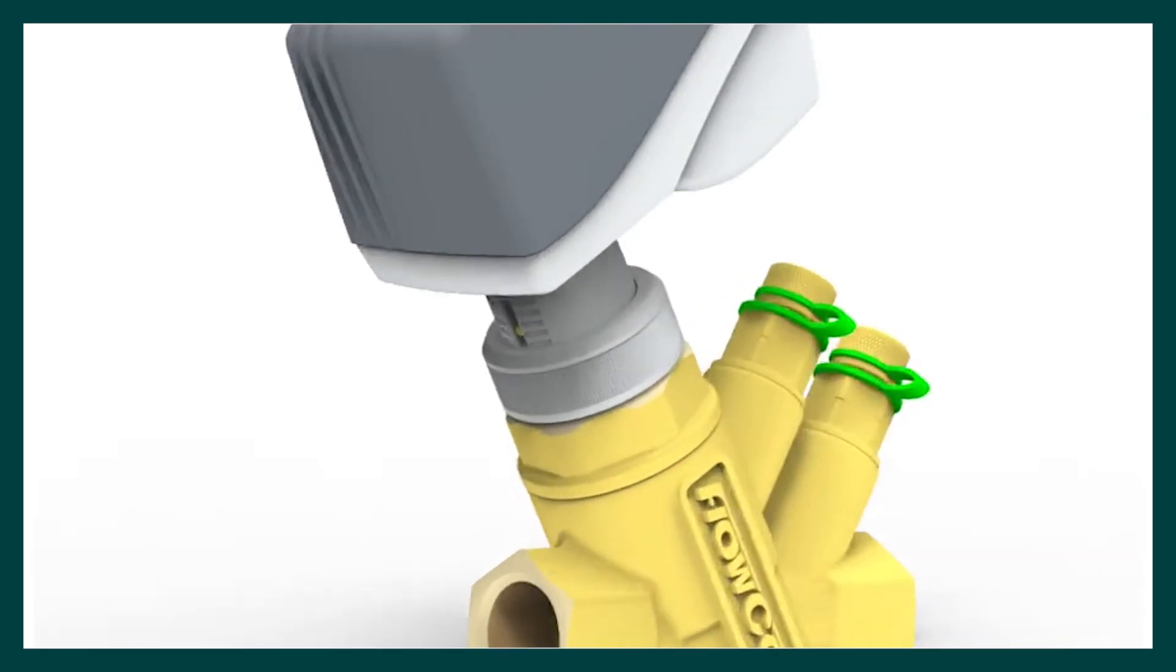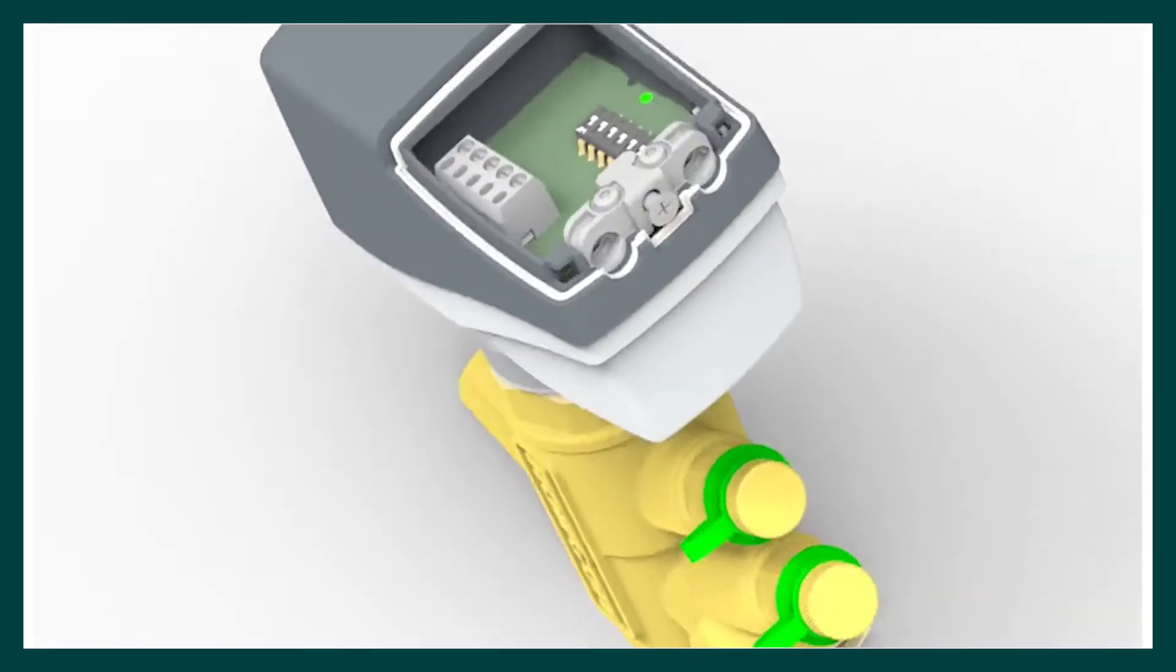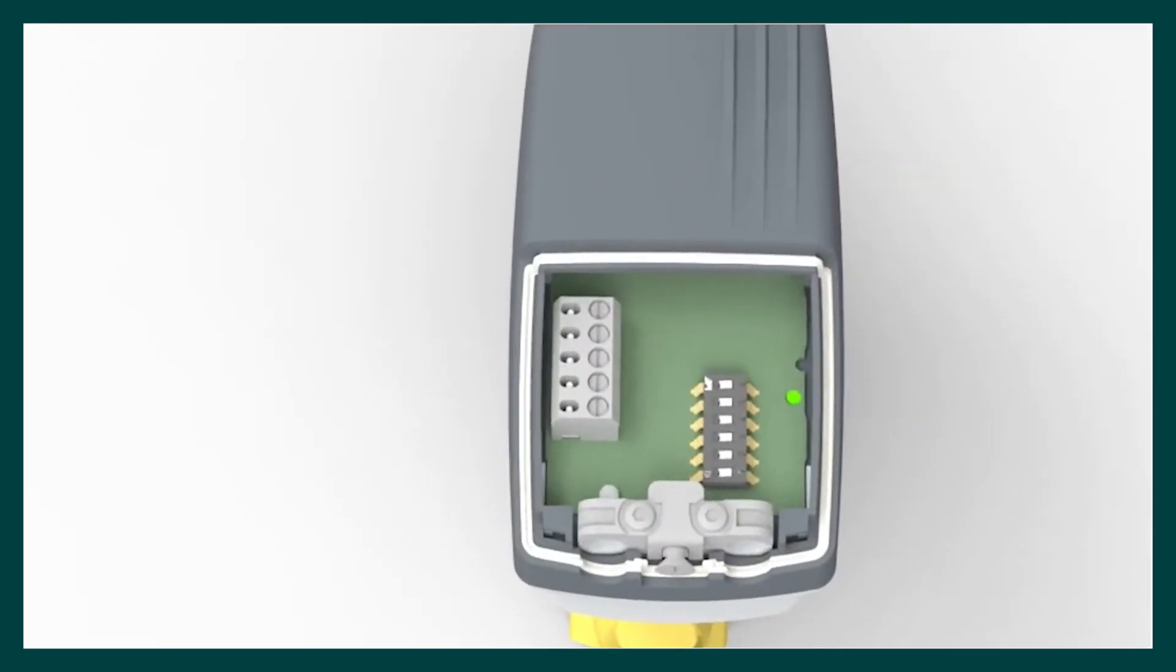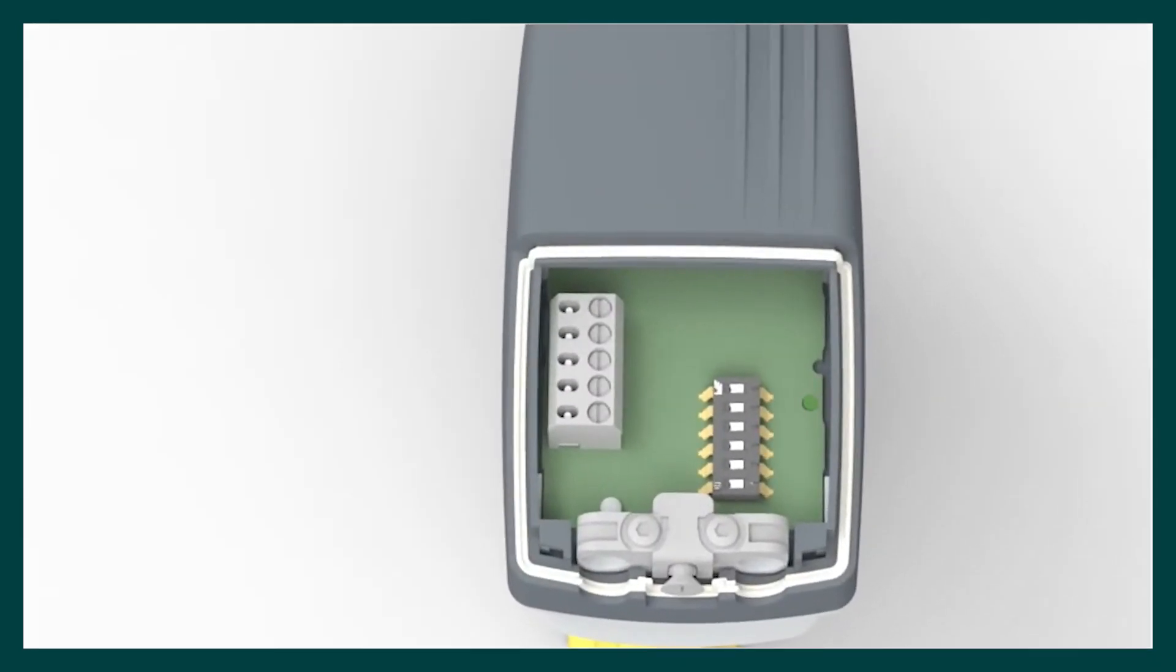During the calibration process, the LED will flash green. Once the actuator locates the closed position, the LED will stay green permanently. No further action is required. The calibrated position will be retained from the actuator memory.